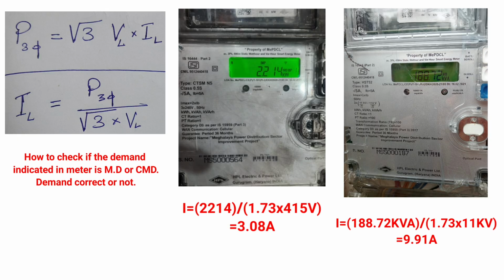kV meter. This meter can actually be used in 11 kV, 33 kV, 132 kV, because the meter itself will not know the system voltage outside. The only thing it receives is a voltage of 110 volt phase to phase, and a base current of 5 ampere and maximum 10 ampere.